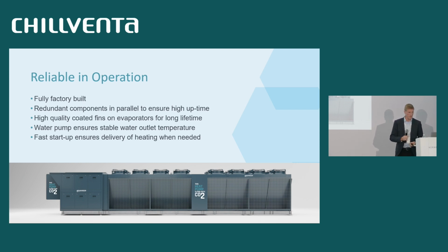And then we have redundant components in parallel to ensure high uptime. We know that end users, customers in a product like this, are looking at the heating. They want to have the heat when they need the heat. So we decided to have a lot of the components in parallel. We have multiple compressors, multiple ejectors, multiple frequency inverters, and as I said, the coils are split in multiple circuits, each with an injection valve. So if one valve should break, we can still provide not full capacity, but a lot of heating until it's fixed and we are back up running.